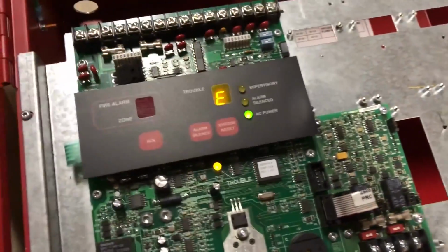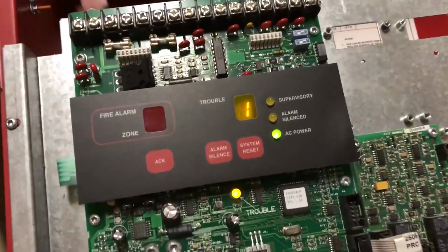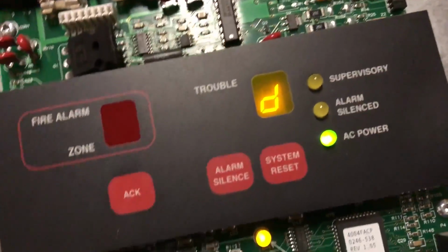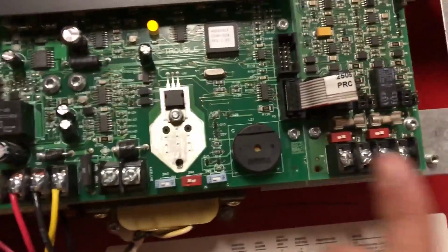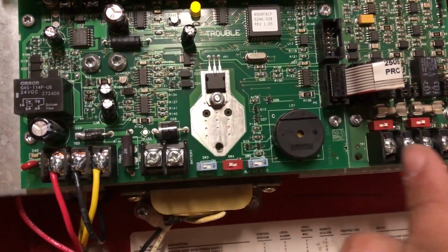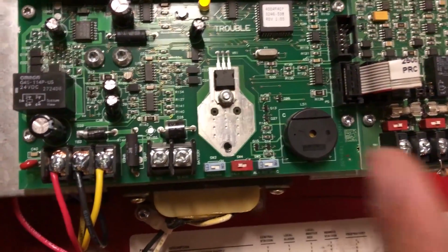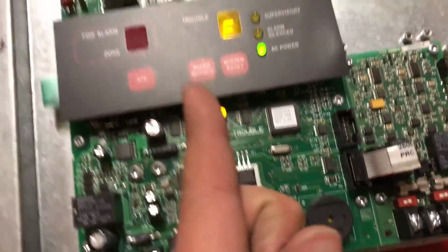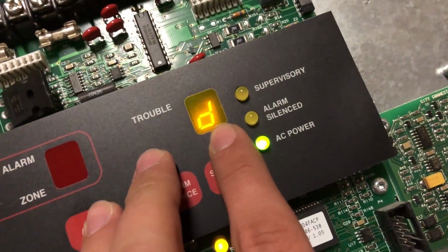Okay, so the panel was just powered up here, and instantly I was hit with a few troubles. In this one, it's not super clear exactly what those are without going to look at the instructions here on the left, and I'll show you that in a second. But some panels have just instructions down here, or LEDs down here, that would say, for example, battery trouble, or so on. And if it has a full LCD, like the newer panels, then it would show exactly what that trouble is. In this case, it's showing 1, 2, D, and that's it. Oh, E and F as well.